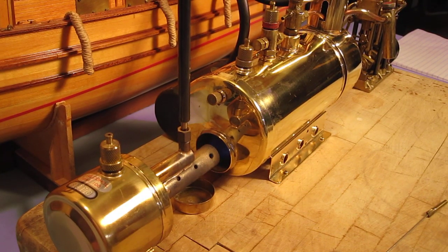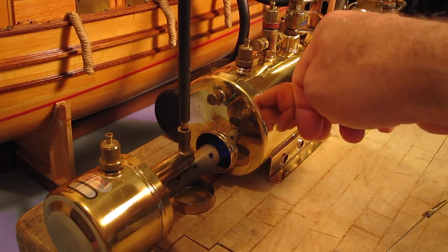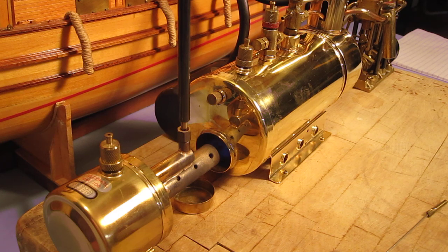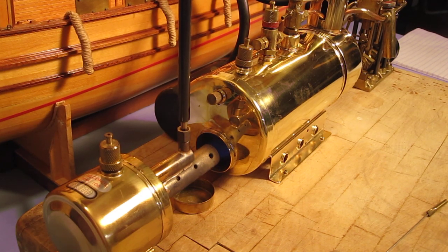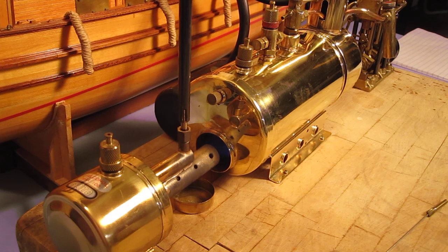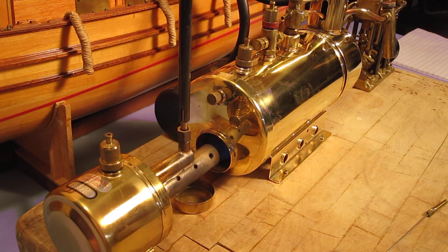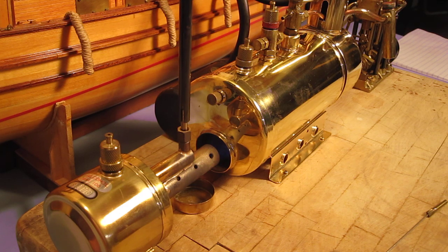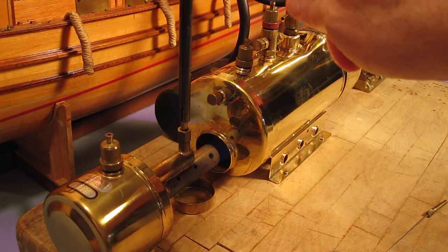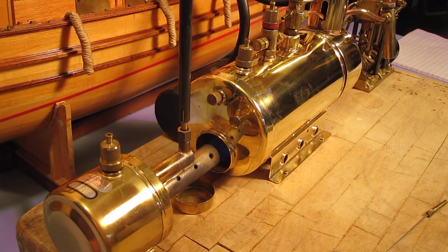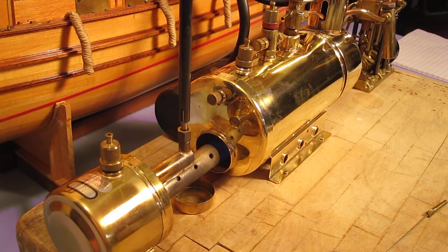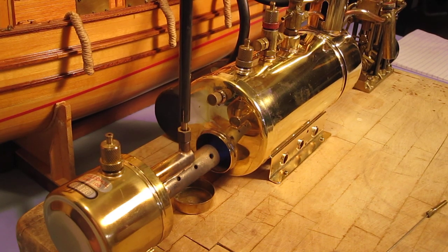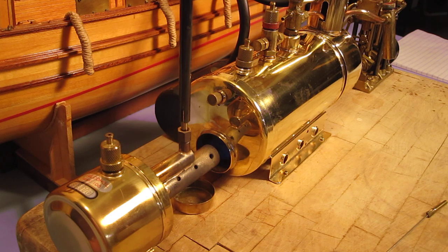Okay, as you can hear I've got the burner ignited and we're going to start preheating the boiler and raising steam. It'll take a few minutes. I've got the burner turned down quite a bit. I ran this yesterday and the burner turned up way too high and I started popping the safeties on the boiler. And when it's too high you get the engine running too fast. So you keep the burner throttled back otherwise you're going to keep on speeding up, having problems controlling the engine.